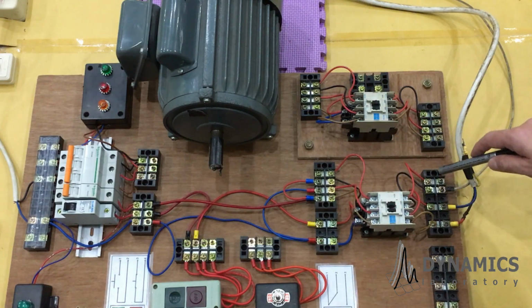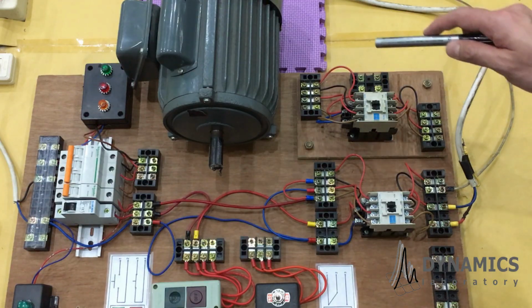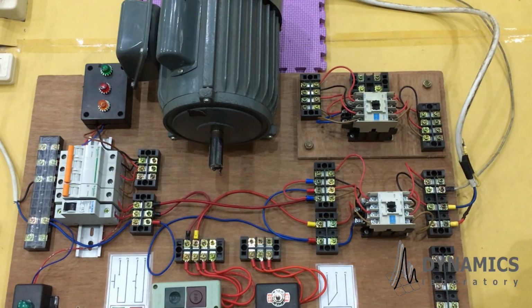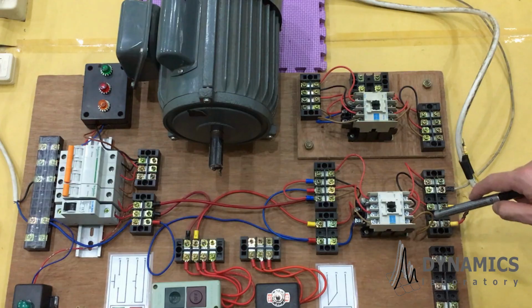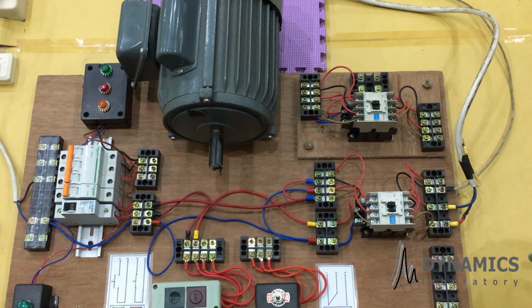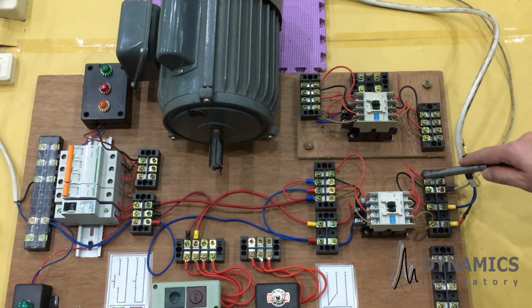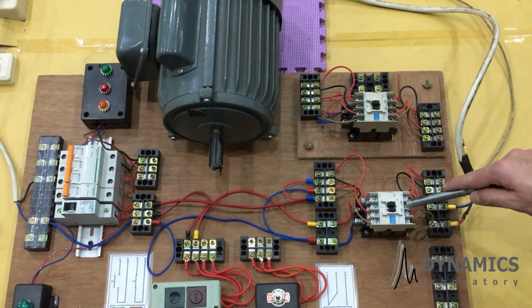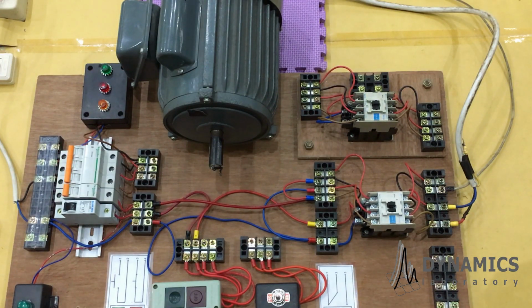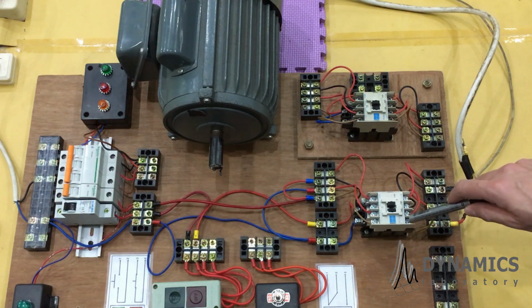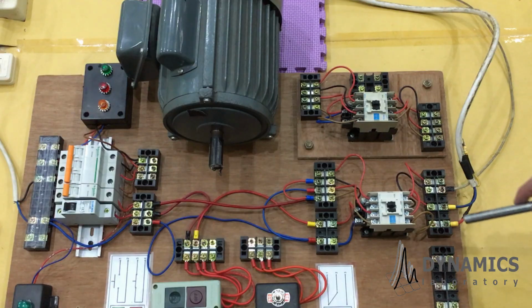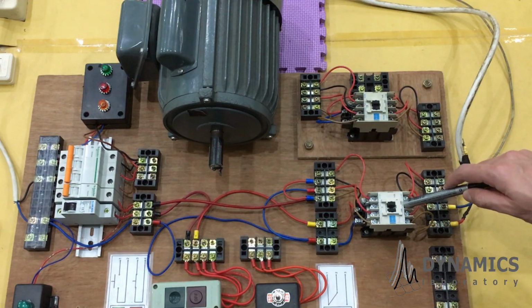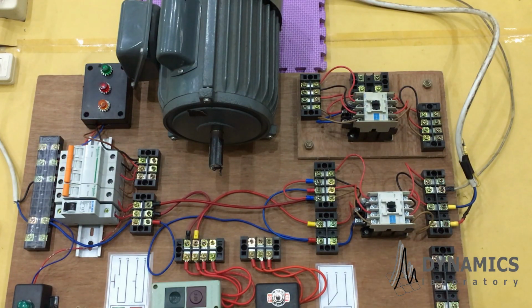This side of the contactor, I have already connected with the one-phase AC motor. And as you can see in here, red and blue cable is to terminal 2 and terminal 4. Both of them are main windings. Meanwhile, auxiliary winding is connected to terminal 6. If the contactor is on, then terminal 2 and terminal 1 is connected. Terminal 4 and terminal 3 is connected. And the same as terminal 6 and terminal 5 is connected.